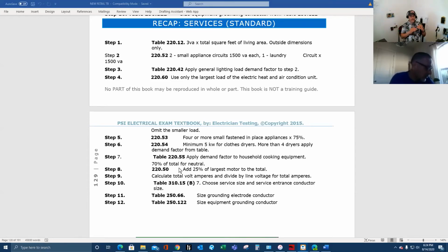There's a cutoff point between what we consider the bare minimum requirements and the other stuff that could be there if elected or present. I can't force somebody to have electric cooking, heating, or drying—they could have gas for all those. So if they have them, I count them, but if they don't, I can't force them. There are some minimum pieces I do require: the lighting load based on square footage will always be there, and there's going to be some small appliance and laundry circuit that's going to be there. Let's talk about how this looks.